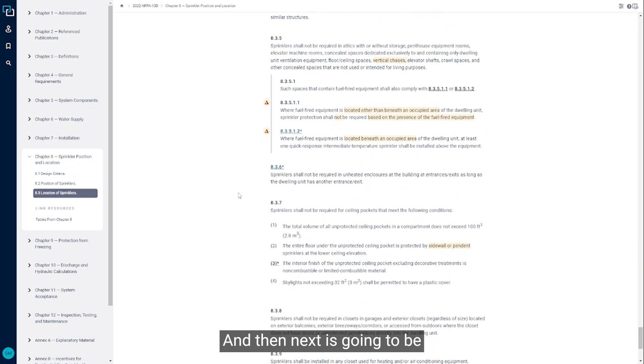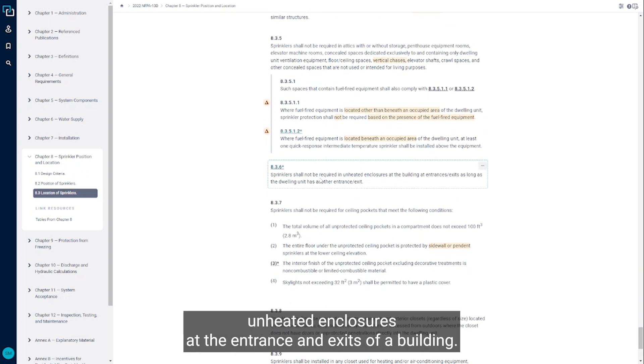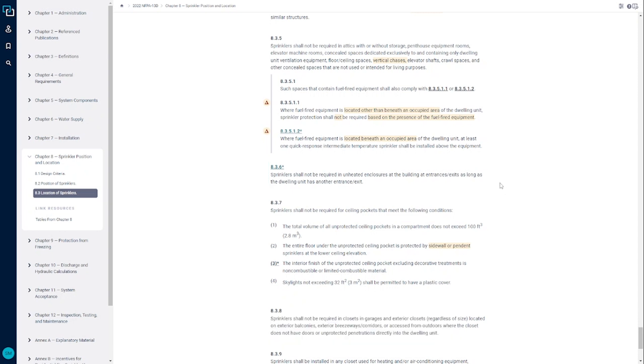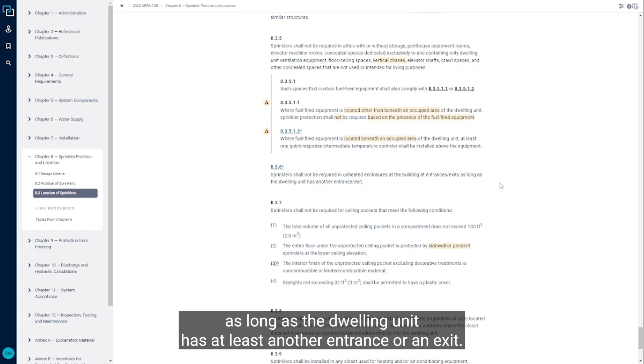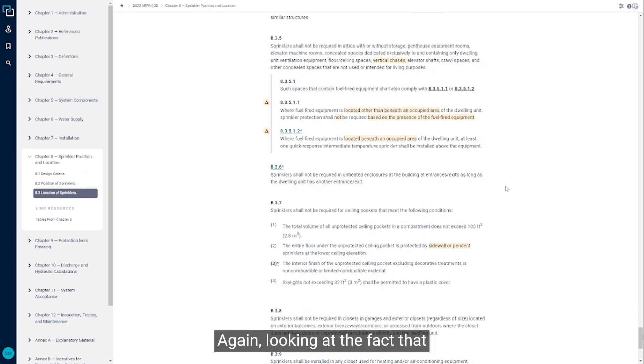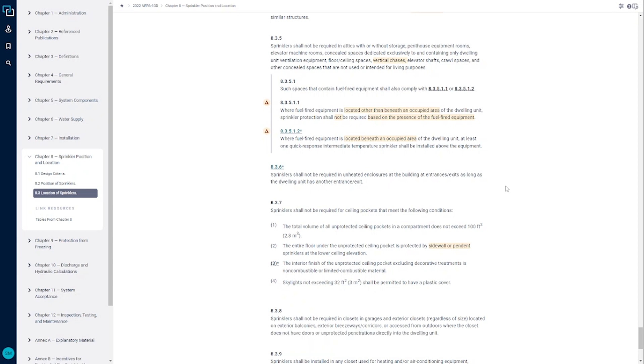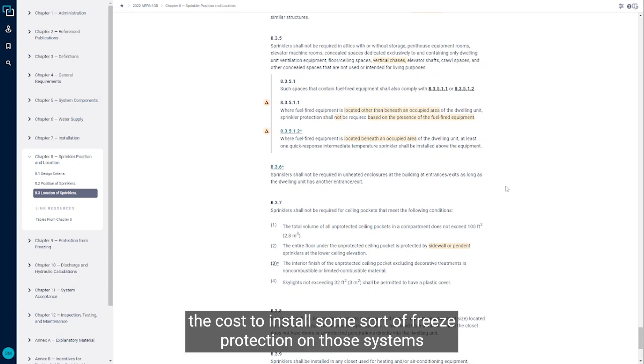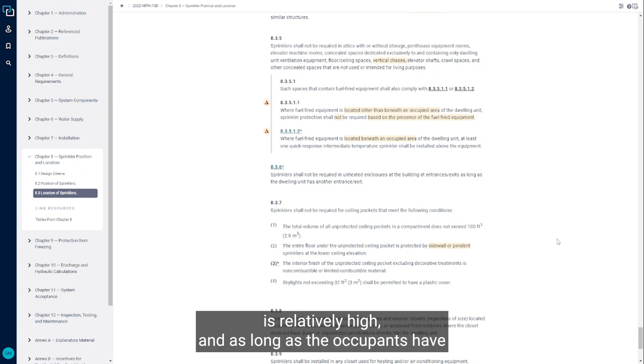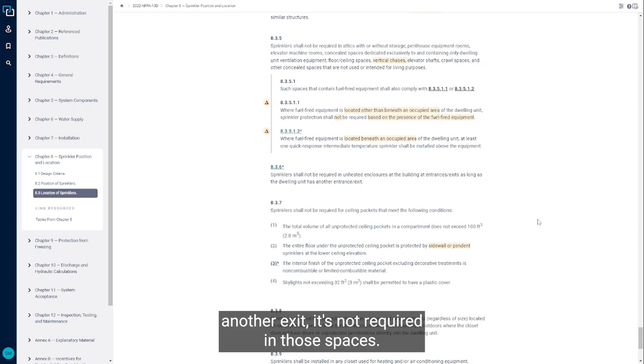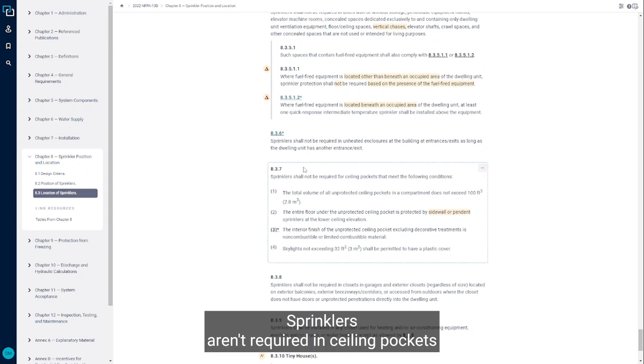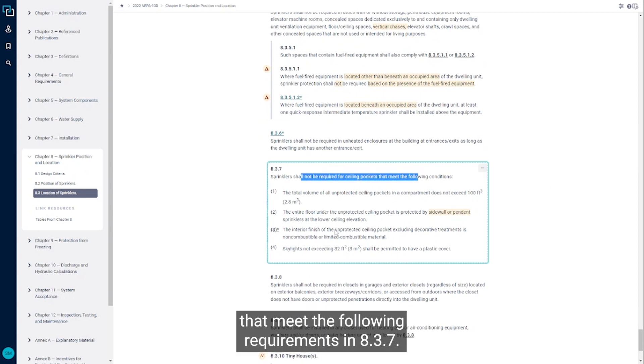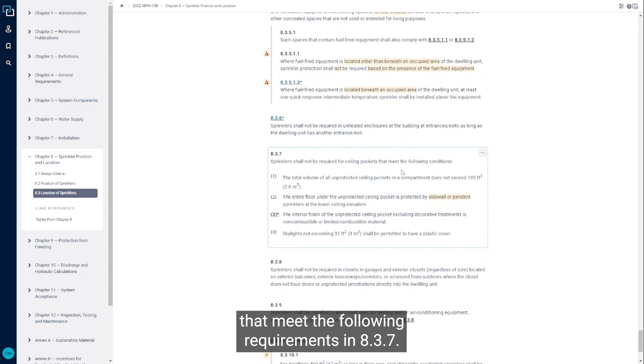Next is going to be unheated enclosures at the entrance and exits of a building. We're not required to put sprinklers in those unheated areas as long as the dwelling unit has at least another entrance or exit. The cost to install some sort of freeze protection on those systems is relatively high, and as long as the occupants have another exit, it's not required in those spaces. Sprinklers aren't required in ceiling pockets that meet the following requirements in 8.3.7.